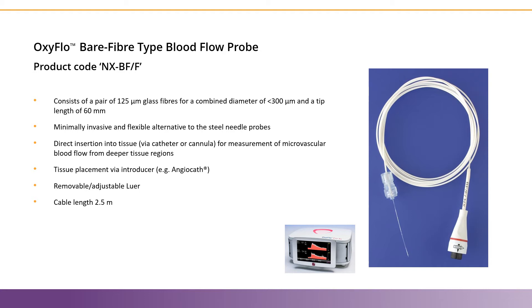They can be cleaned with 70% alcohol, and the white coiled cable you see in the photo on the right is approximately 2.5 meters long. Since these fibers are made of glass, the reusability of these probes is limited, as they are more fragile than the other OxyFlo sensors.